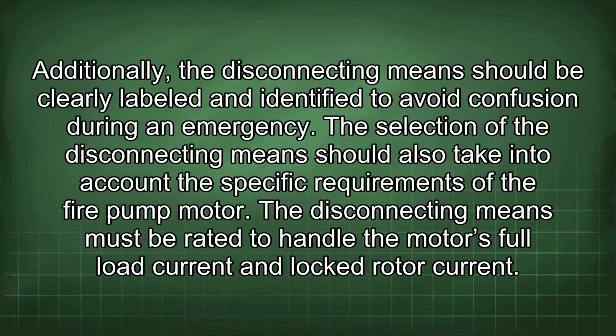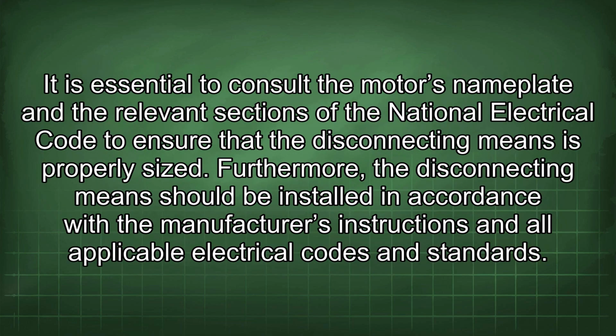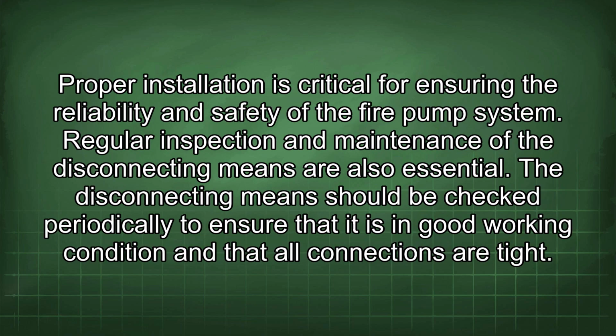The selection of the disconnecting means should also take into account the specific requirements of the fire pump motor. The disconnecting means must be rated to handle the motor's full load current and locked rotor current. It is essential to consult the motor's nameplate and the relevant sections of the National Electrical Code to ensure that the disconnecting means is properly sized. Furthermore, the disconnecting means should be installed in accordance with the manufacturer's instructions and all applicable electrical codes and standards. Proper installation is critical for ensuring the reliability and safety of the fire pump system.